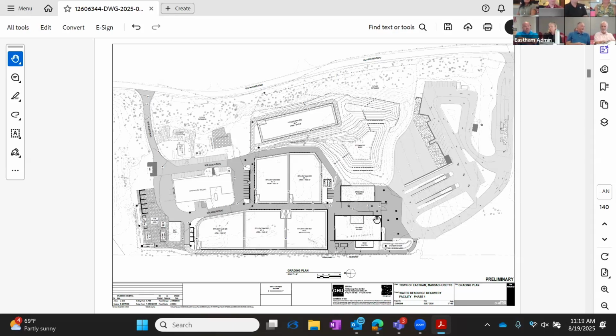I worked at one plant, different wastewater, but they literally used a regular garbage can to collect the grit. Then maybe it was like a 1 yard for the screenings, so it really depends. That plant was probably 10 times the size of this one, it was like 1.4 MGD. Just by comparison, I'm working on a project right now where they haul offsite 4 to 6, 30 cubic yard dumpsters of screening and grit material a week. But that's also a 50 MGD pump station serving a combined sewer system. So there's a full range out there.